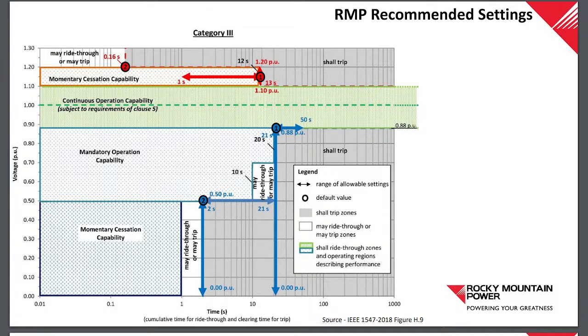If we're looking below the green and to the left, the mandatory operation capability, you can see it goes down to 50%, and then the x-axis on the bottom is your time. So you can see it's mandatory operation from 50% for 10 seconds, and then momentary cessation to 0 for up to a second. But then the gray, that's where it's going to trip. No matter what happens, it's going to trip. And you can see it's all over the place.